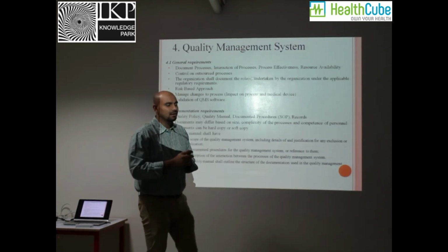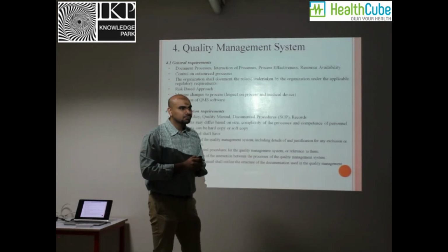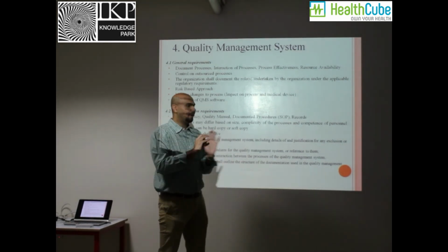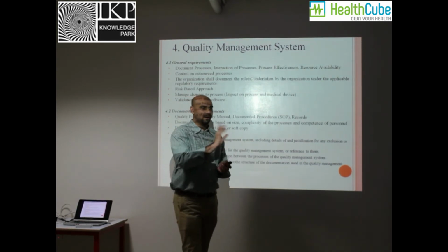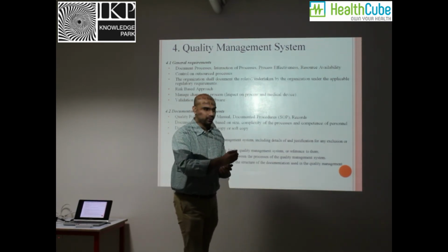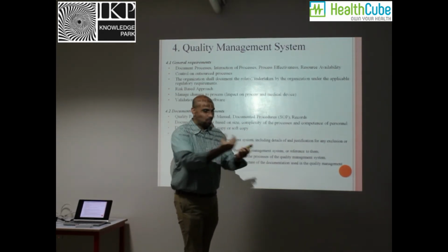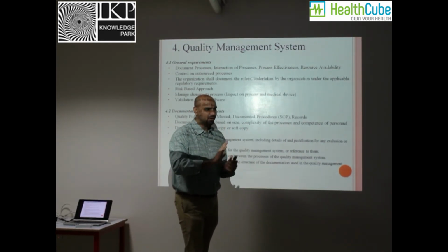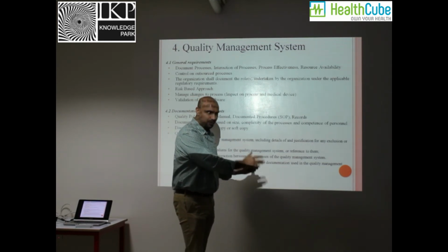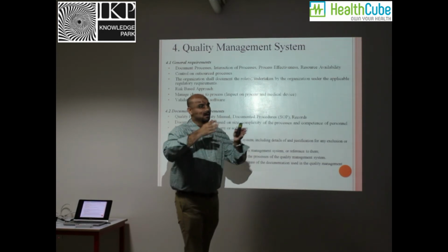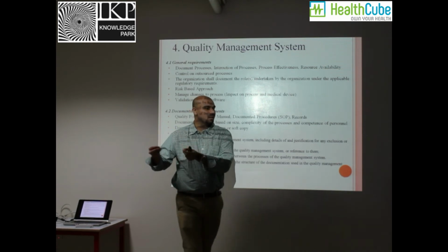Is there a classification that is followed here? 13485 has no classification. When you talk about regulatory, when you talk about registering your product, it is all about classification. When I talk about something like CE, if your product is an IVD, the approach to register that product for the European market is going to be completely different compared to registering a medical device.